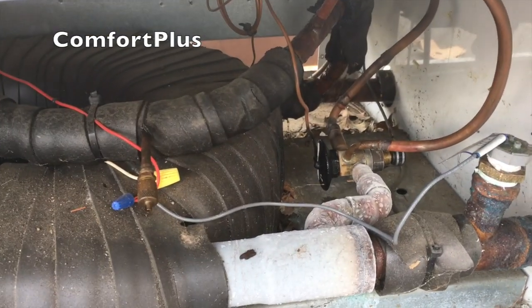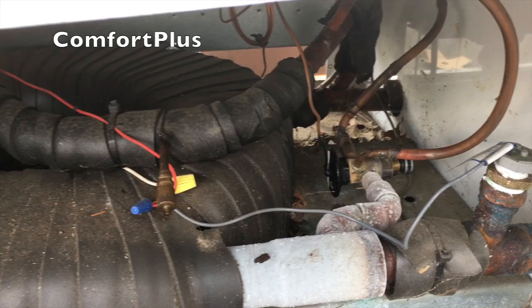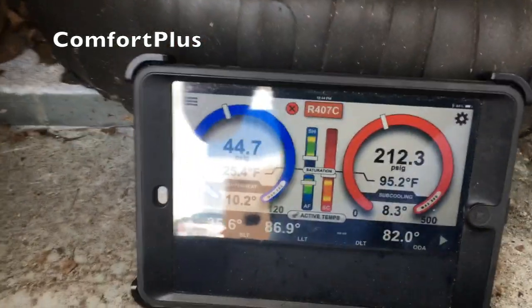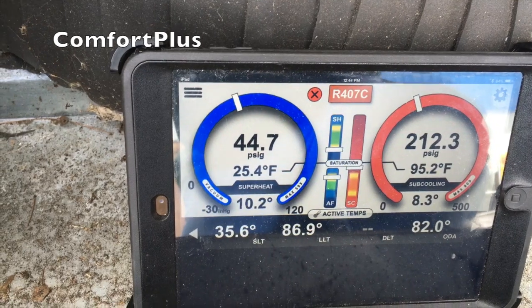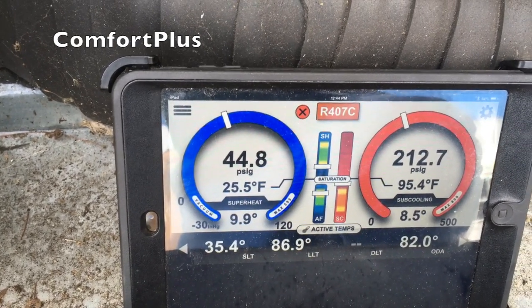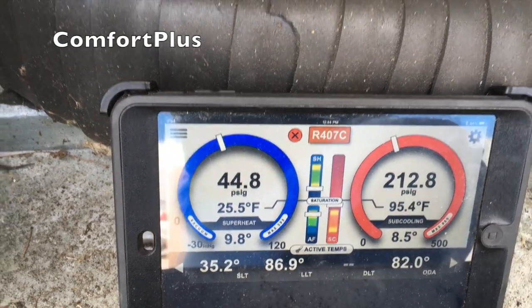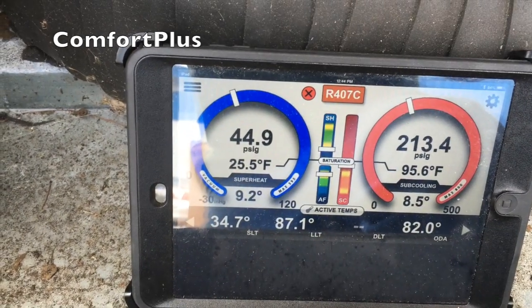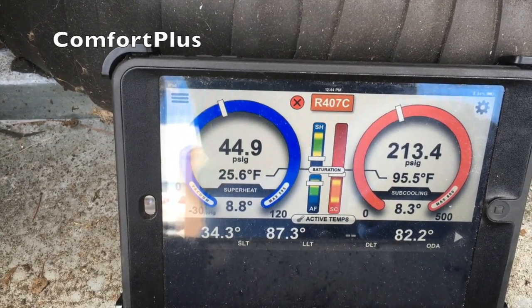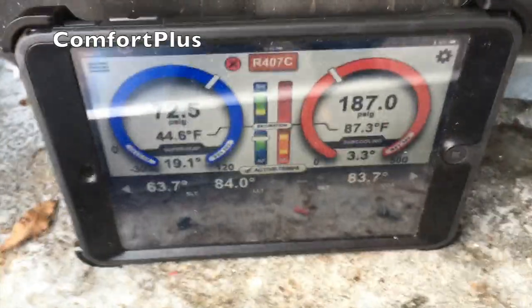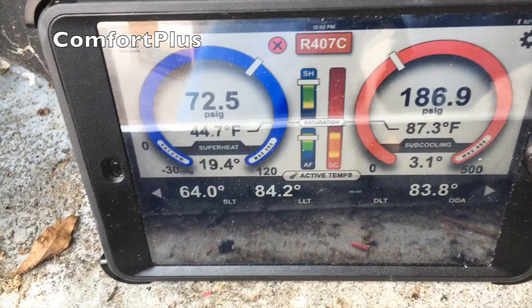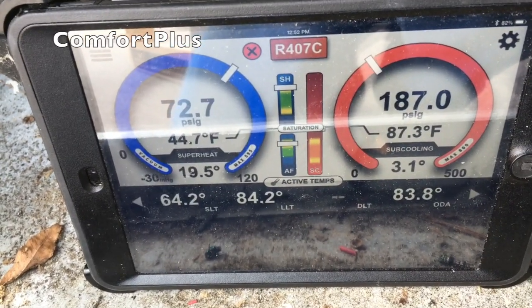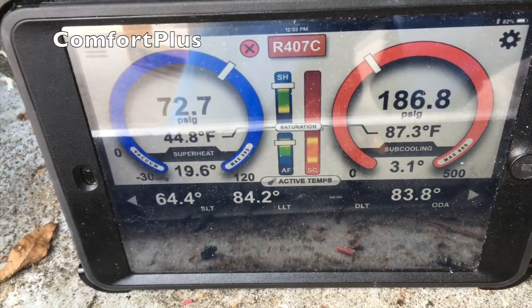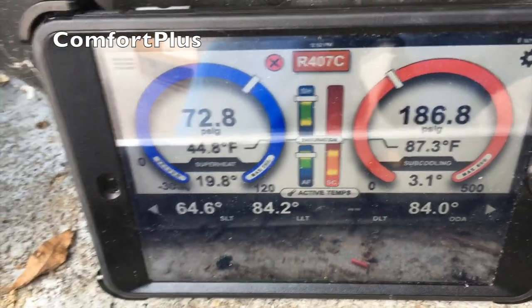So that TXV is shut off a lot more than it was when I got here, so I don't know if it was ever adjusted right or if somebody lowered the water temperature after the refrigeration circuit was all set up. But I'm going to keep an eye on it here and see how she runs for a little bit. He's got the load in our washing, so it's going to be using some cooling to get rid of that solvent. Good thing this puppy's 3-phase, because it's been off for a little bit and it hadn't bled around, so if it cycles pretty quick, it'll be a big temperature difference or a big pressure difference.